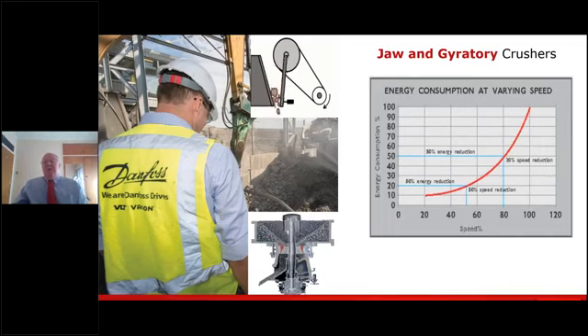So what will happen is the control of the variable speed drive will sense the load on the motor, and then it will actually reduce the speed to the requirement. So if we just look at a 30% speed reduction on the motor, you have a 50% energy reduction. So quite a substantial saving.